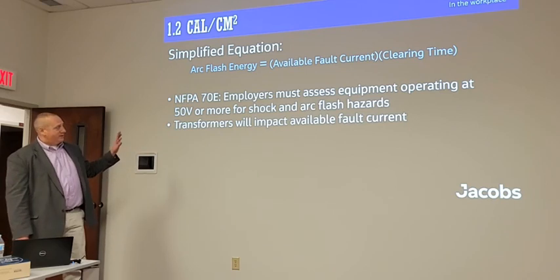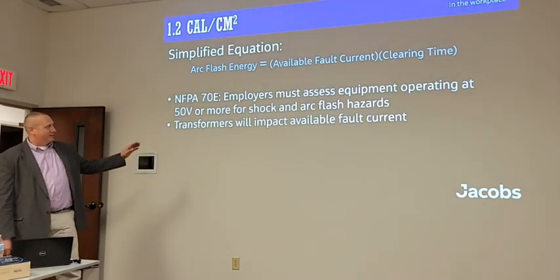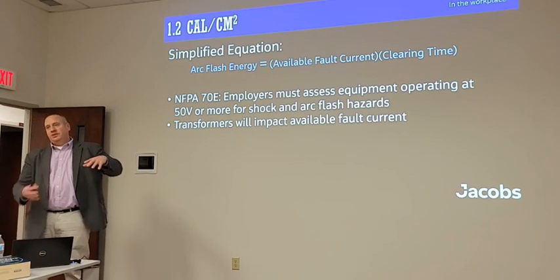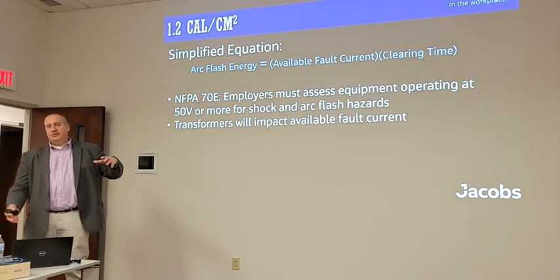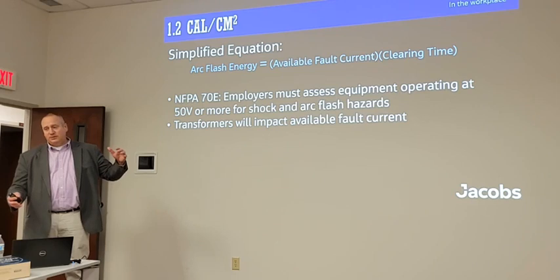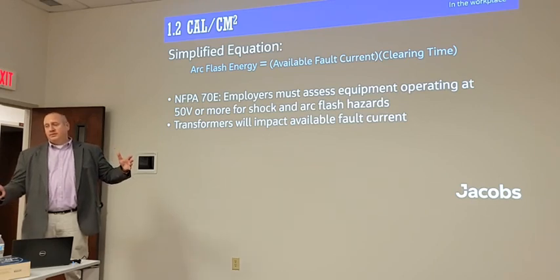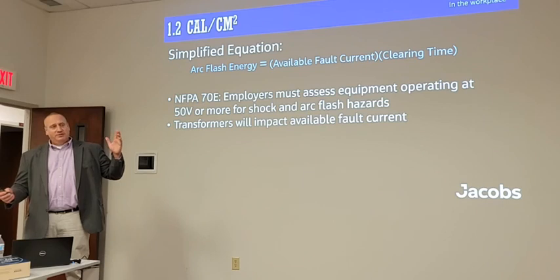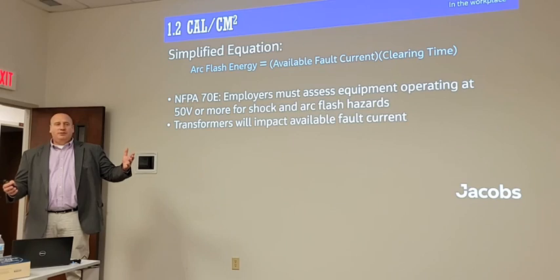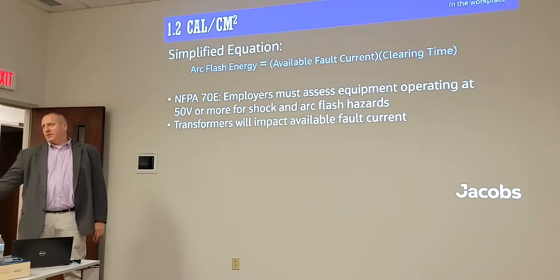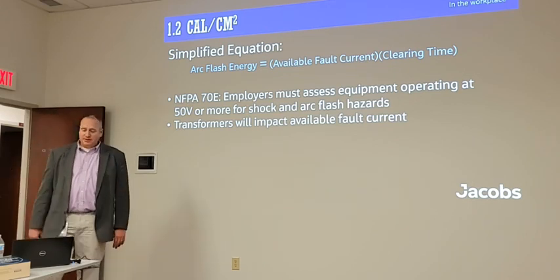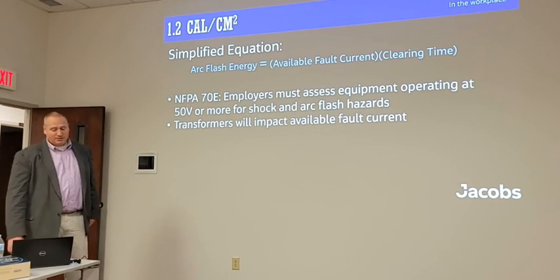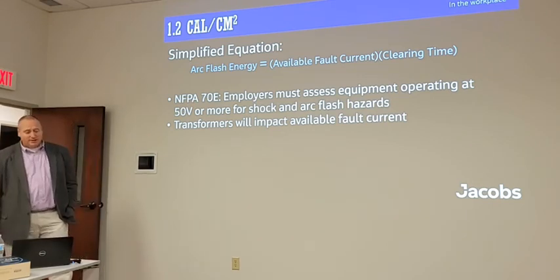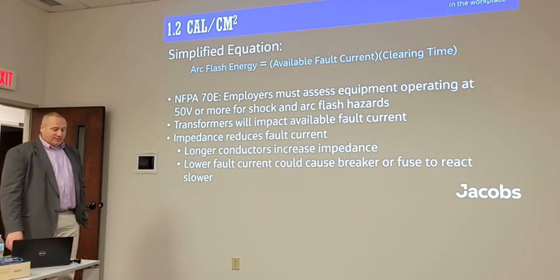One easy one that I realized from the beginning, didn't have a problem with this: anytime you run into a transformer, downstream of the transformer, now everything's changed and you've got to redo the analysis. There's a lot of scenarios for a medium voltage unit substation, for example, where you've got a medium voltage fused switch on the primary that could be 0.8 calories per centimeter squared, and then the immediate downstream main 480 volt breaker may even be over 40 calories depending on the size of the transformer, or certainly more than 1.2 calories per centimeter squared. So transformers impact the fault current. But also impedance reduces fault current.